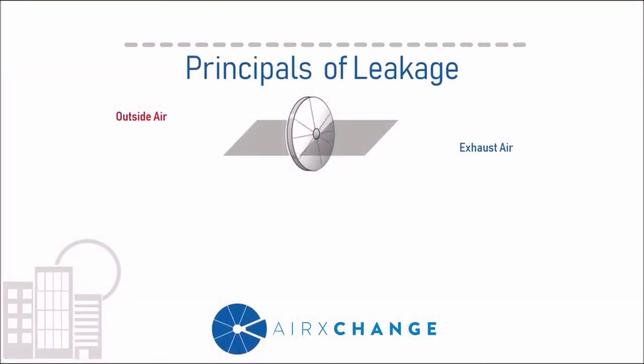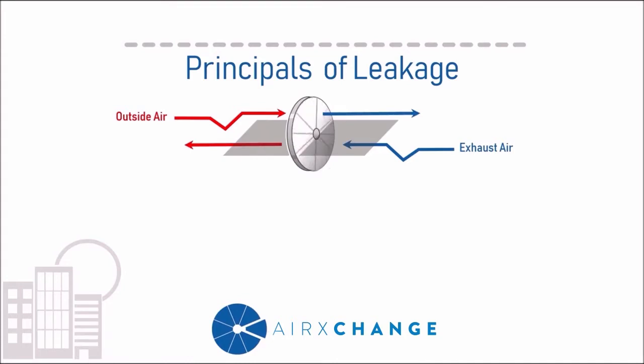Let's take a look at the operation of an energy recovery wheel. As you bring outside air into the space, you're using that air to dilute the space air with fresh outside air and displacing the stale air through the exhaust system. Starting with the exhaust air stream, that air naturally wants to progress through the wheel, allowing the wheel to recycle that energy and condition the incoming air. During this process, there is a portion of air that never actually makes it into the resultant air stream and bypasses back into the space where the air was taken from.